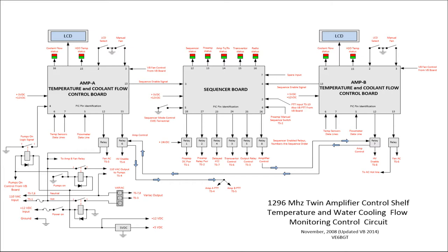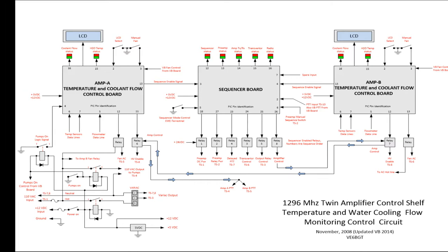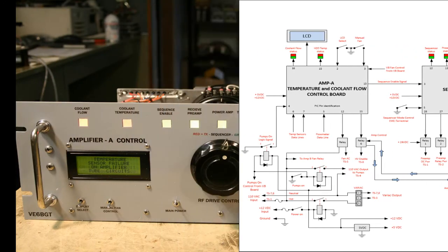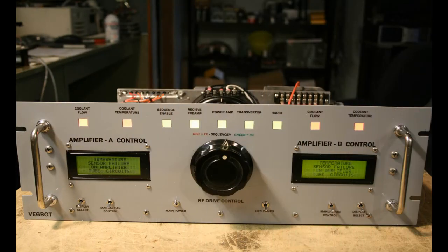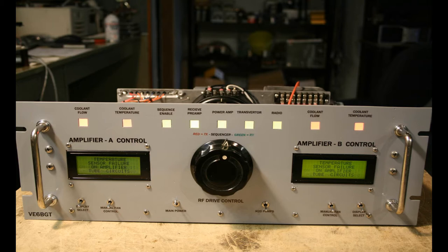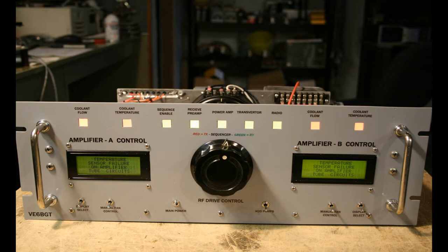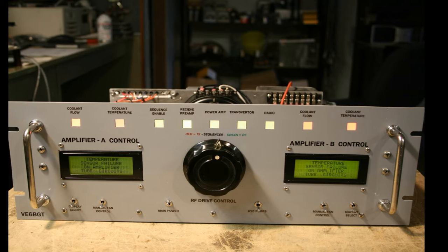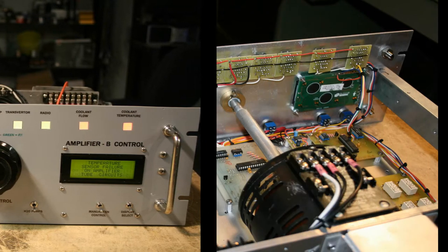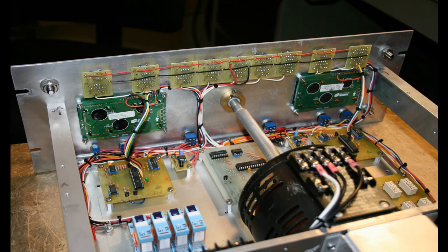It pretty well takes care of itself all around. There are a number of LEDs on the front panel which go between green and red, which indicate the status of the sequencer going from receive to transmit to transmit to receive. Also an alarm circuit such as coolant flow and coolant temperature. The two LCD displays tell you the status of the individual circuits such as water temperature, flow rate of the coolant, and also this is where you adjust the set points for alarms and fan turn-on points.